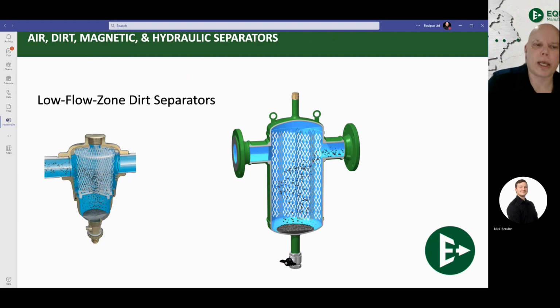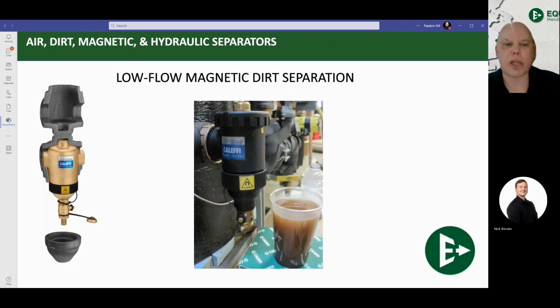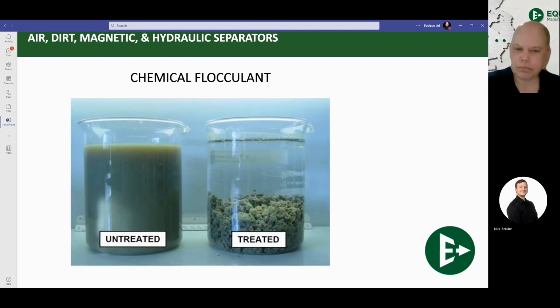So here's a little diagram of what it looks like. You've got dirt particles in the water. It's coming through. When it hits the dirt separator, it creates a pressure drop. You have big pressure up, it's a great big open area. You get that pressure drop, and then gravity kind of takes over from there. Whatever dirt is in the system is going to be heavier than the water, so it's going to be pulled to the bottom. If you have a magnet down there, even better, because the magnet is going to pull that magnetic material, such as the magnetite, which is extremely small, all the way down to the bottom to get that out. As it's pulled out, it gets caught inside the dirt separator. You do your flush, and as you'll see, you'll get something that pops out that kind of looks like chocolate milk.